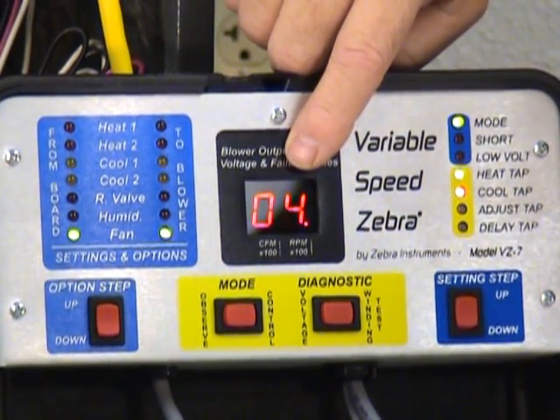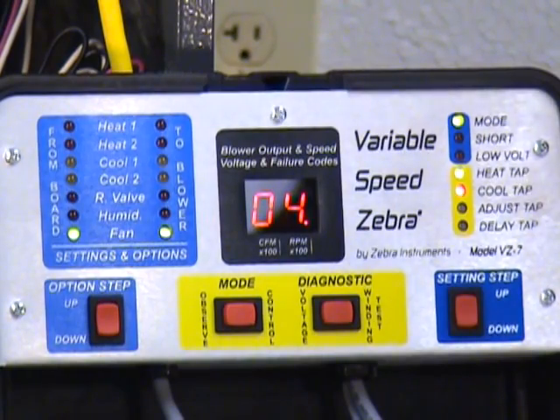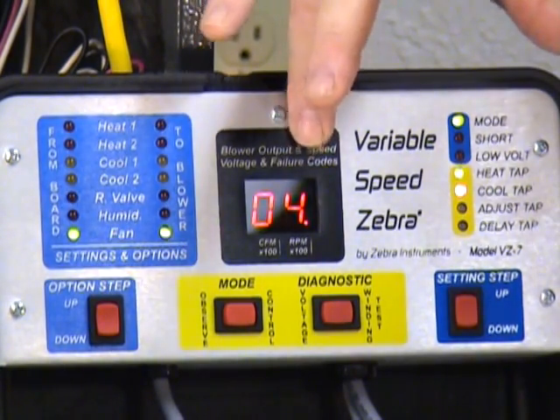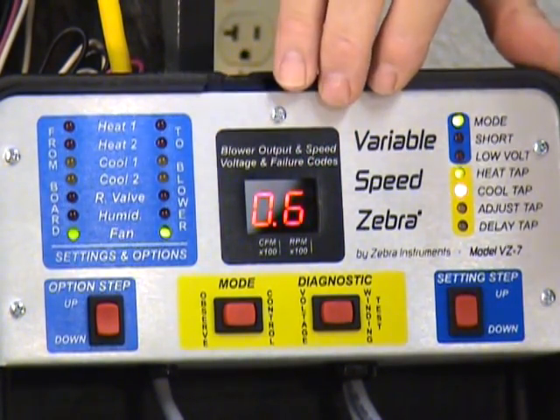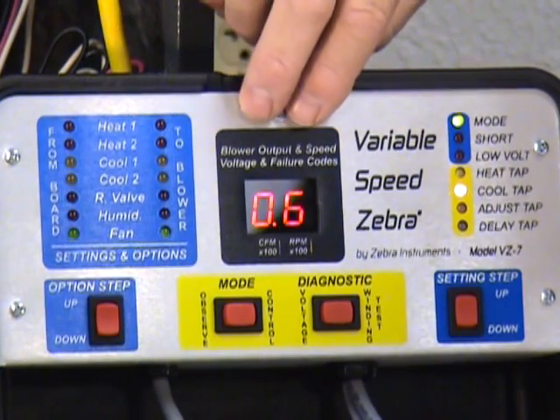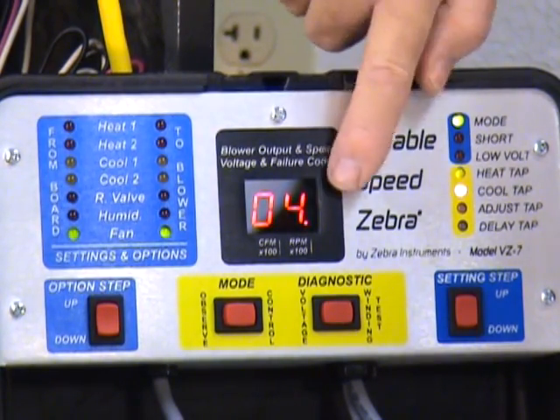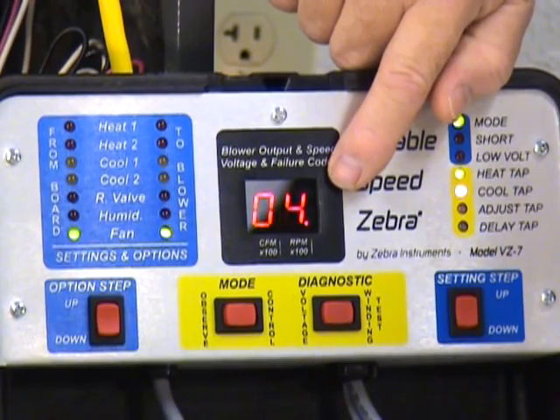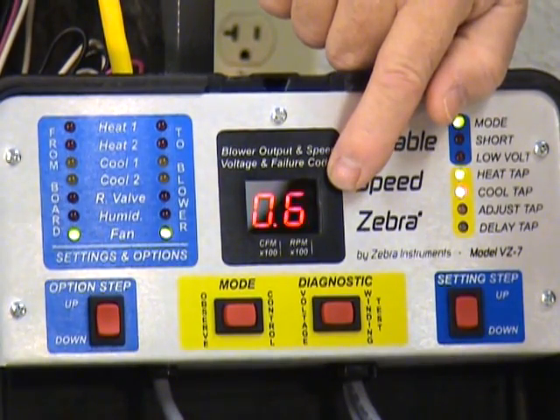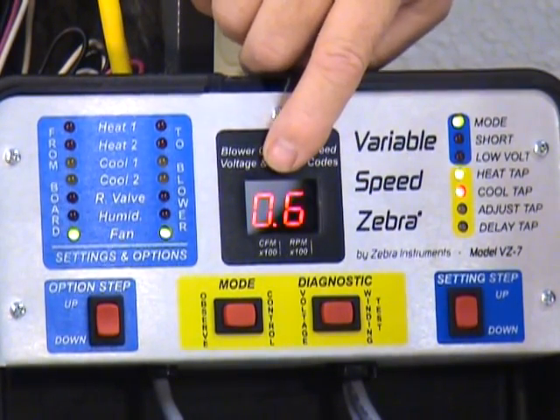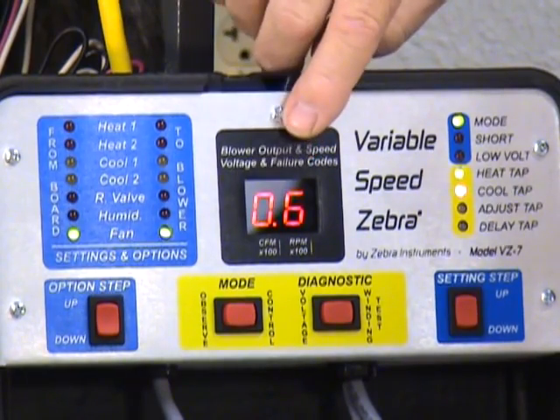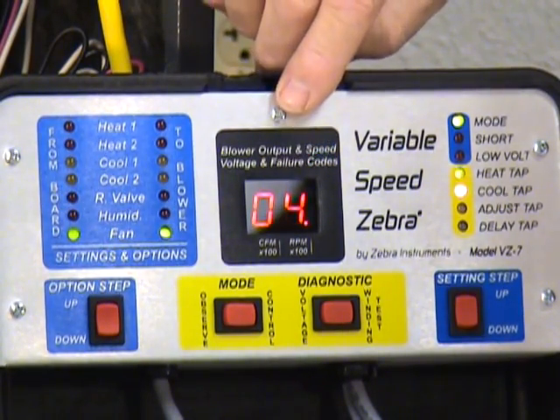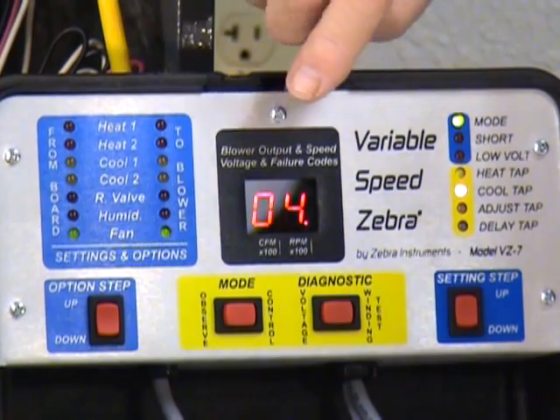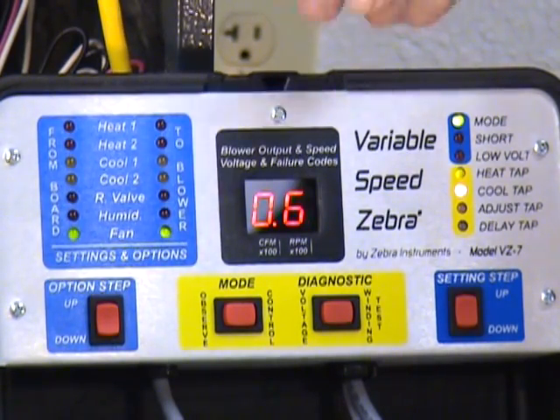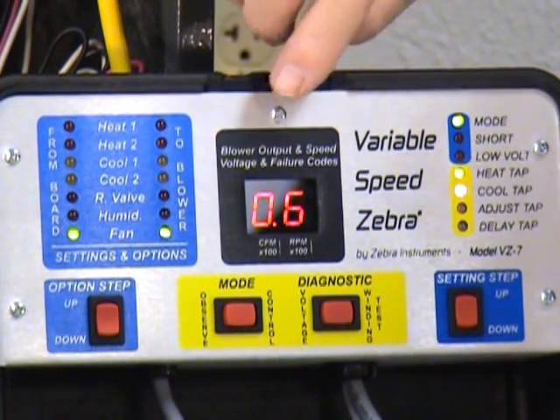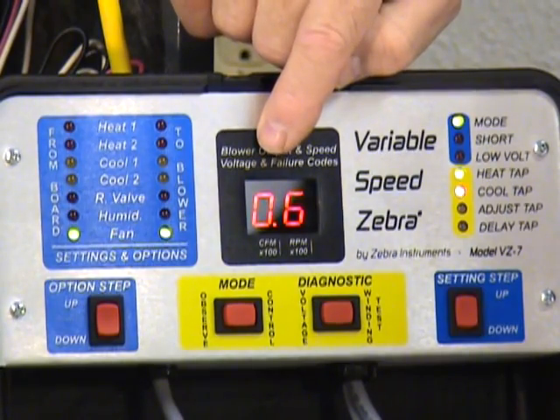There is a bit of a time delay for the electronics coming out of the motor to be decoded by the microprocessor in your variable speed Zebra before it'll display that. So what this is telling us right now is this motor is running at 400 RPM. It's producing 600, remember you multiply by 100, it's not 0.6 and it's not 4.0, it's just 4 or 6 times 100. It's producing 600 CFM of air.